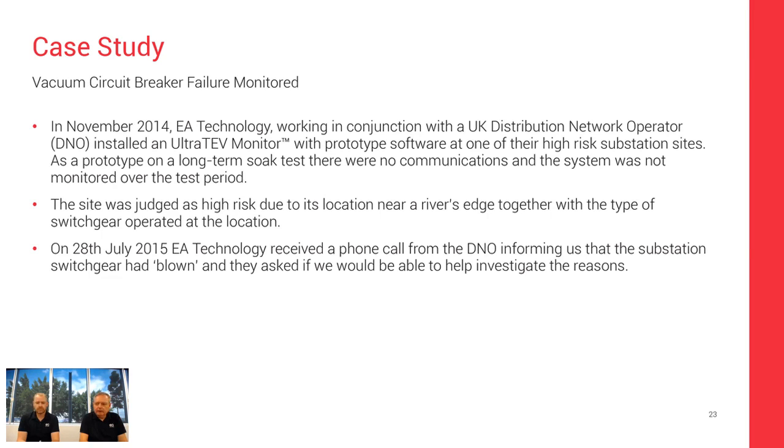This is one where in the UK, EA Technology, working with one of the DNOs, had installed one of our monitoring systems. It was part of a prototype and long-term testing. Nobody had really taken the trouble to instigate the communication, so nobody was actually looking at the data. This is a classic case of people seeing a project to monitor switchboards as putting the monitor on, whereas really the project starts when the monitor is installed, because you've got to be looking at the data.